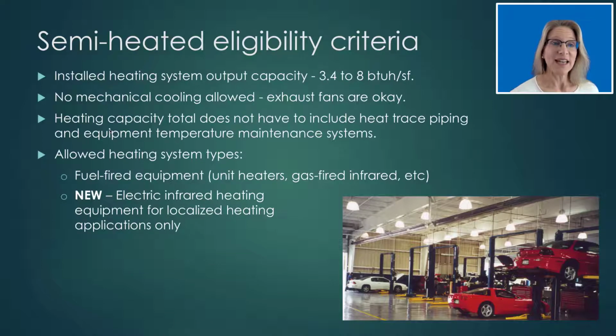What is new is that you're now allowed to have electric infrared heating equipment as long as it is only being used for localized heating application only. So for example, in this image you've got an automotive repair facility and they have radiant heaters over the work bay. That's the type of system that we're talking about.